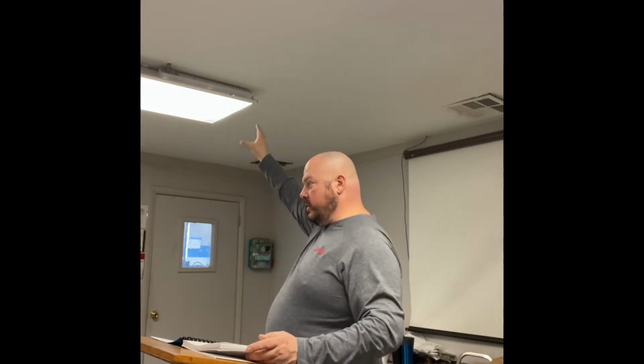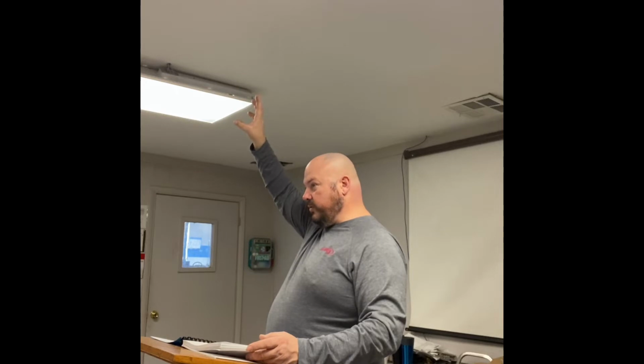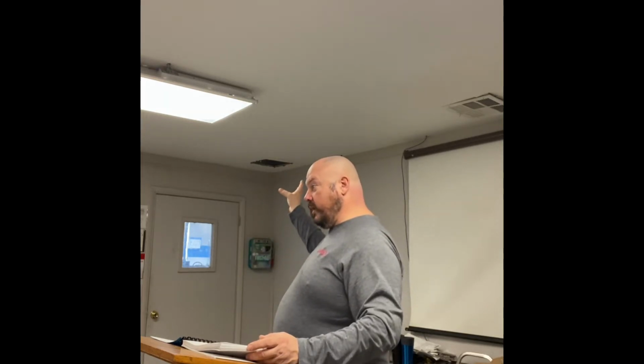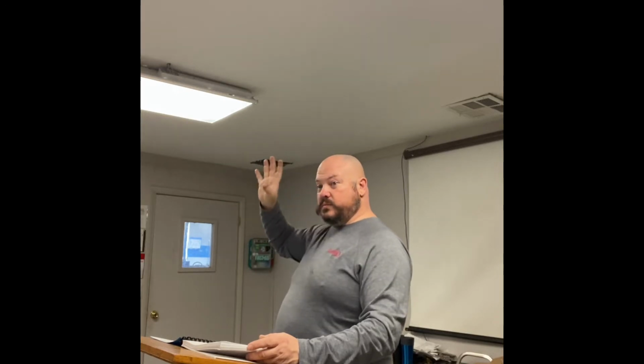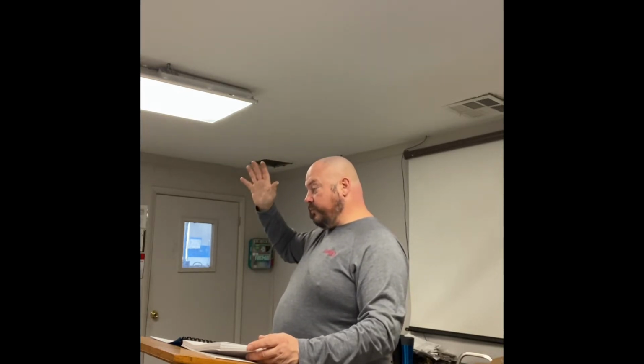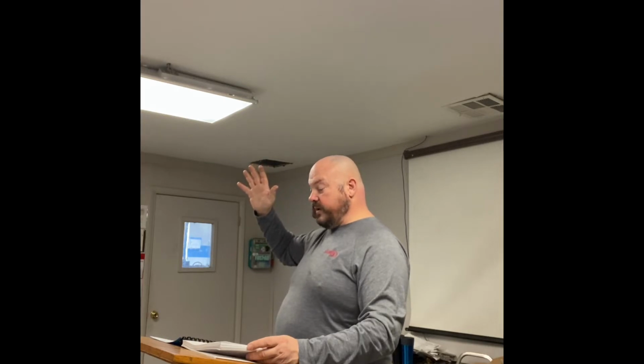Okay? When you have all 4 of those, all you need to do is let the system run for just a little bit. Because what we need is for the duct work to be tempered correctly. Most of our ductwork here in Arkansas runs through the attic. So in the middle of summer, it's probably gonna get a little warm, right? We want enough air conditioning to run through that pipe to cool it off, to make it to where it's not going to be stupid hot and changing our temperature difference, okay?